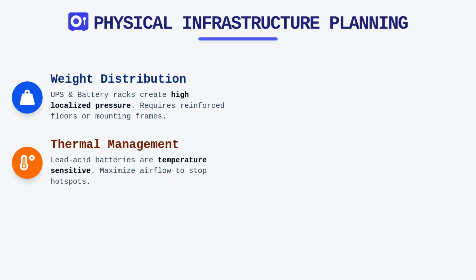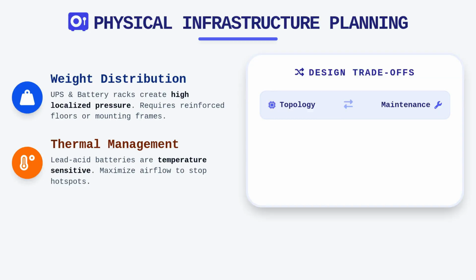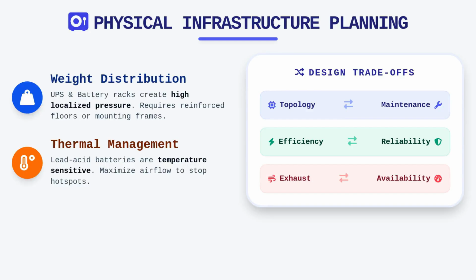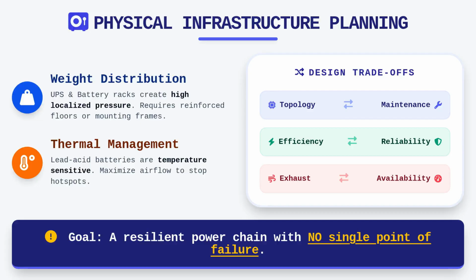If you place a UPS in a restricted space, you must provide sufficient airflow to prevent hotspots that lead to premature component failure. Every design choice, from the selection of the UPS topology down to the routing of the generator exhaust, involves a trade-off between reliability, efficiency, and maintenance accessibility. You are ultimately tasked with constructing a resilient power chain where no single point of failure can jeopardize the availability of the facility you are supporting.